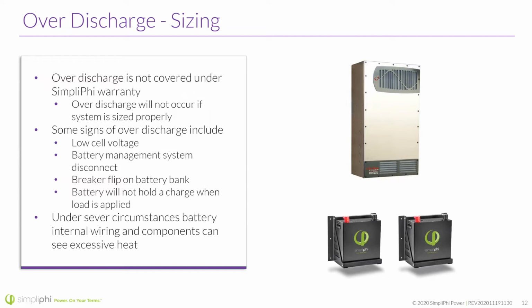Under severe circumstances, battery internal wiring and components can see excessive heat. So I've seen it before. If you're pulling way too much current out of these batteries, you might see some excessive heat, not on the cells most likely, but on the wiring and the components within the battery. So those can all be signs of over discharge, and that's something to watch out for.